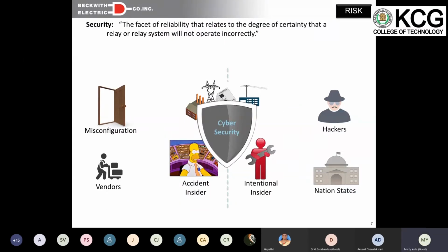Just to give you a basic definition of this risk thing - security, how you define security: the facet of reliability that relates to the degree of certainty that a relay or a relay system will not operate incorrectly. What happens if a relay operates incorrectly? If there is a fault, the main purpose of the relay is to detect that fault and operate, go and open the circuit breaker to isolate the faulty system. If it incorrectly operates, that means it did not clear the fault, you'll see smoke coming out from the switch yard. But suppose it acted erroneously and tripped off a large power plant, a gigawatt power plant - then a nearby city will be blacked out.